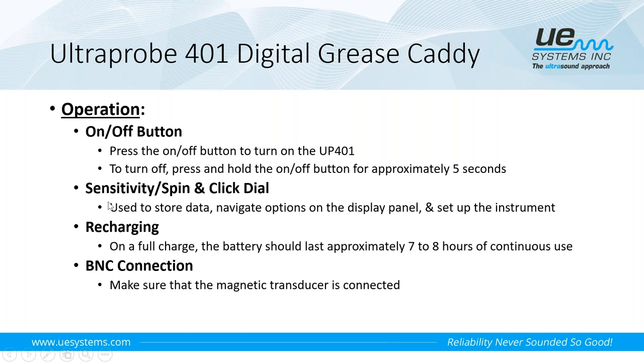The sensitivity spin and click dial again serves a dual purpose. It's a way for us to press in and release, and that's how we're able to navigate around the display to make our different adjustments, from the sensitivity to our function bar, or maybe to navigate the route. So if we need to advance forward or skip over points, all that's done via the sensitivity spin and click dial. We mentioned the recharging, again, continuous use of 7 to 8 hours on a full charge. And then the BNC connection, just make sure that our magnetic mount transducer or contact probe is connected.